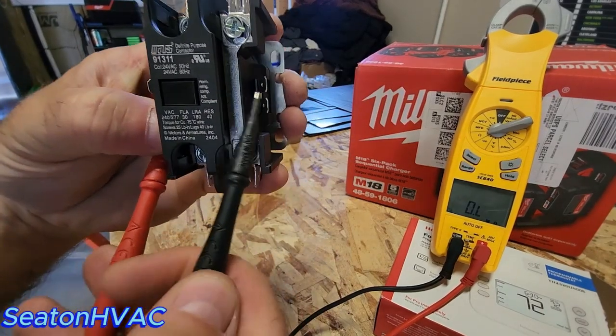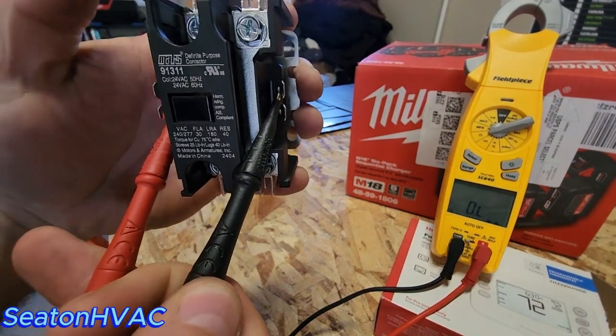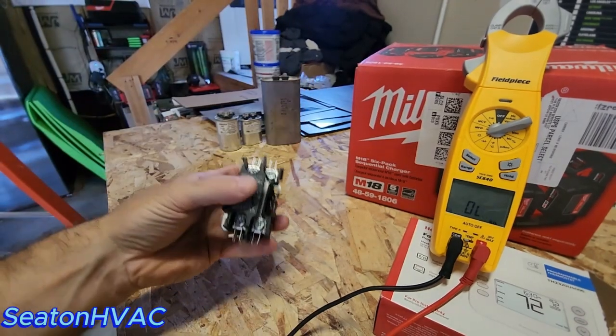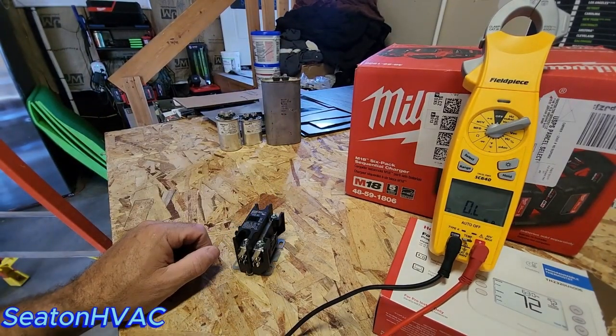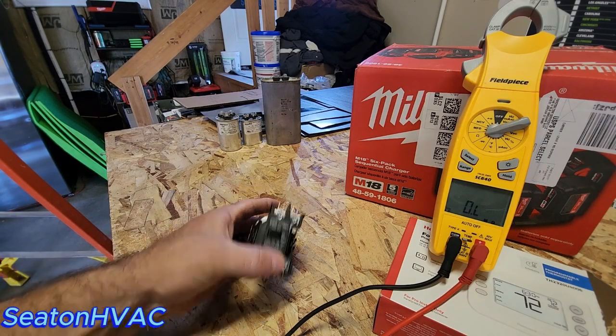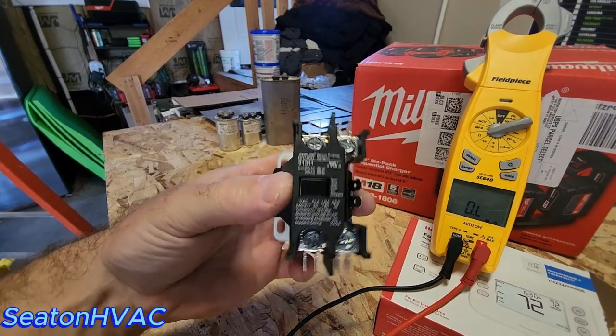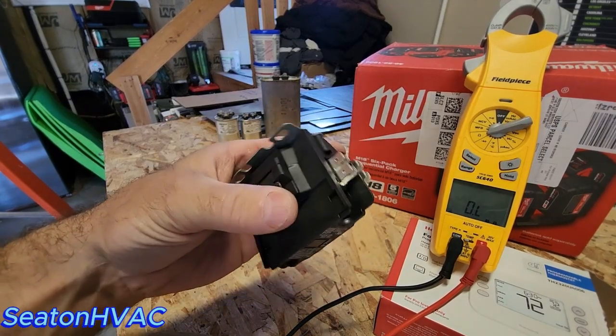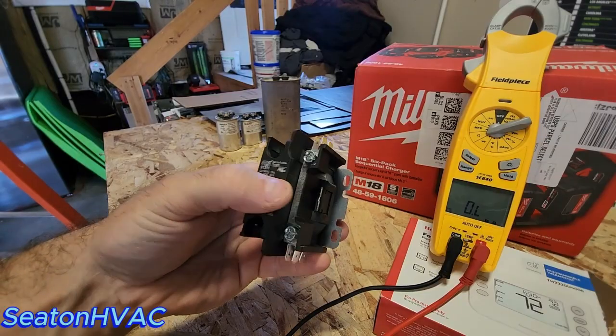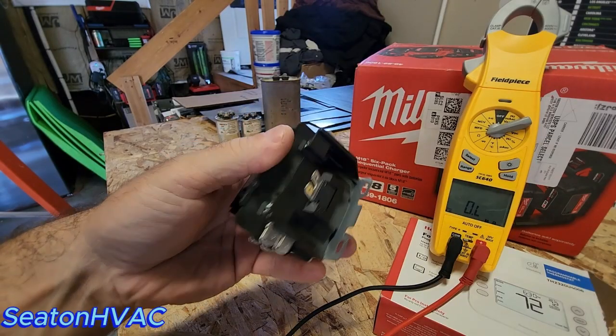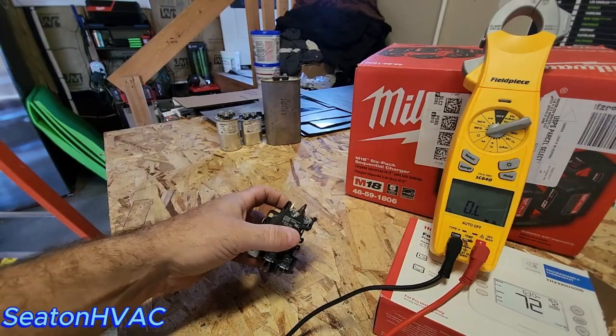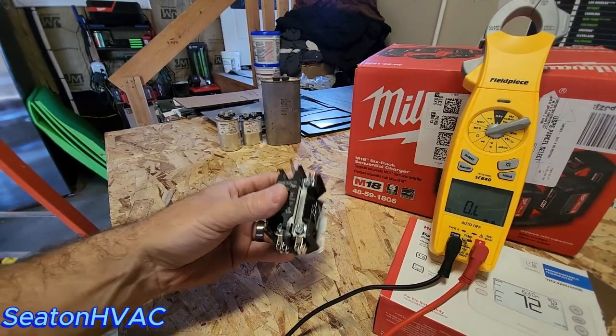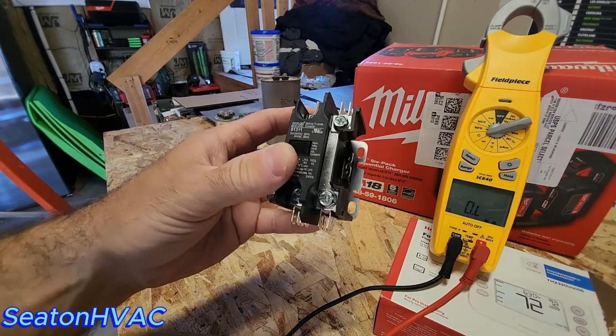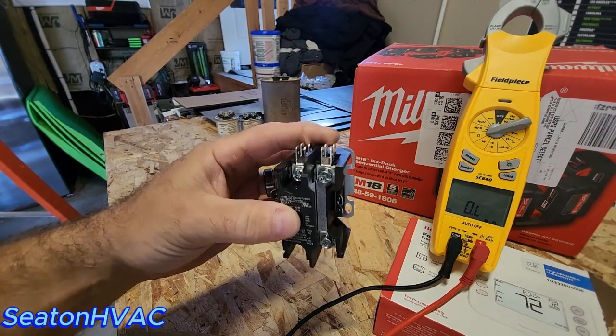Let me show you where I put my leads. One there, and then one on the opposite side. That's your 24 volt side, and that'll read your ohms for you. Anything in the teens is pretty much good. You start dropping below 10, it might be time to recommend a new coil, a new contactor to the customer. You may disagree with me. Somebody's going to get on and say, "Oh, dude, six ohms is fine." But you're not going to find anything above 20 usually on these. So anything in the teens is usually good. Good rule of thumb. I say 8 to 18 because I haven't found any that are over 18. Not on the stuff I work on anyway.